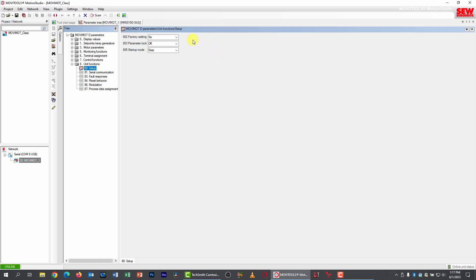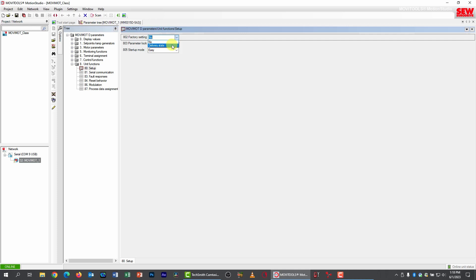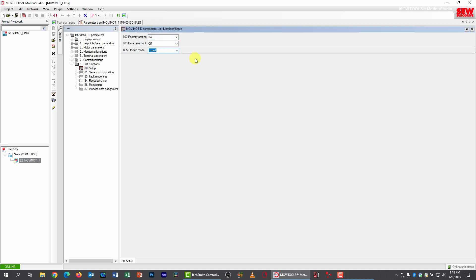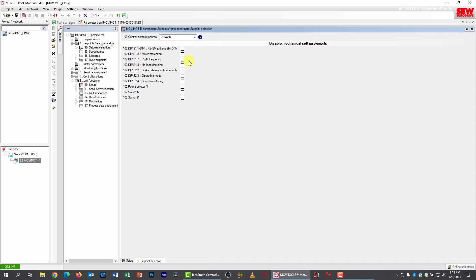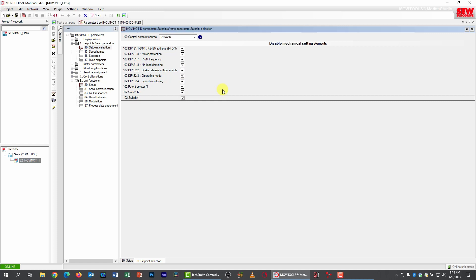This contains parameters for both factory resetting and changing mode. I go to parameter 802 and change it to delivery state — and by the way, when you do this you get no warning; Movimot is immediately wiped and returned to factory default. To change from Easy Mode to Expert Mode, I go down to parameter 805 and change it to expert. We're now in Expert Mode. The first thing I want to do is disable my mechanical controls, so I go to parameter group 1, subgroup 0, setpoint selection — every checkbox I check disables the corresponding mechanical control.